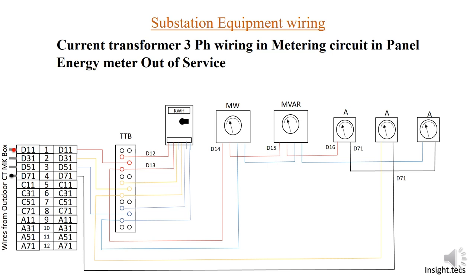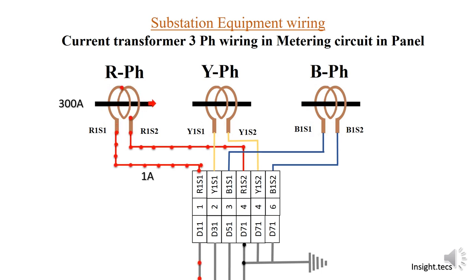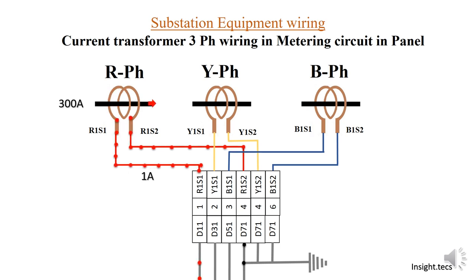Here you can see d11 coming in and d71 coming back. The current flows into the neutral and we get the neutral back. So starting from d11, the current has flowed through the metering circuit inside the panel, come back through d71, into the neutral, and back into the current transformer — completing the full circuit as you can see here.